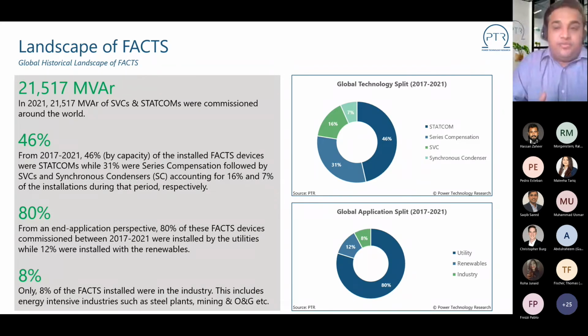Talking about the historical landscape of FACTS, especially the last 5 years, you can see that in 2021 we saw more than 20,000 megavolt-ampere reactive of FACTS commissioned around the world. Overall, across every FACTS technology, including STATCOM, series compensation, SVCs and synchronous condensers, close to 50% of installations over the last 5 years were STATCOMs, which was not the case in previous decades.